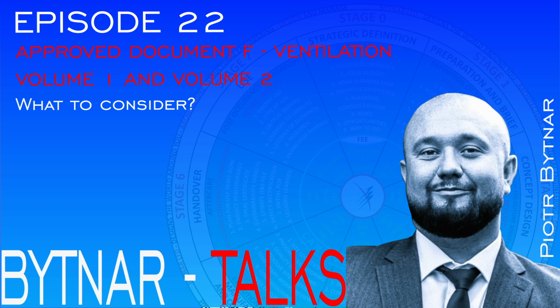The requirement of as high as possible but not lower than 400 millimeters from the ceiling ventilators for naturally vented premises is also applicable here, but the passive stack ventilation terminals should be in the ceiling. Air supply for offices should be at least 10 liters per second per person, or 1 liter per second per meter square of floor area. Common areas in the office will need half a liter per second per meter square of the common area, or natural ventilation opening of at least 2% of the floor area.